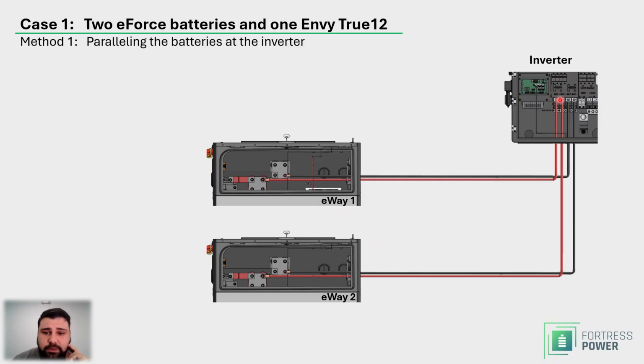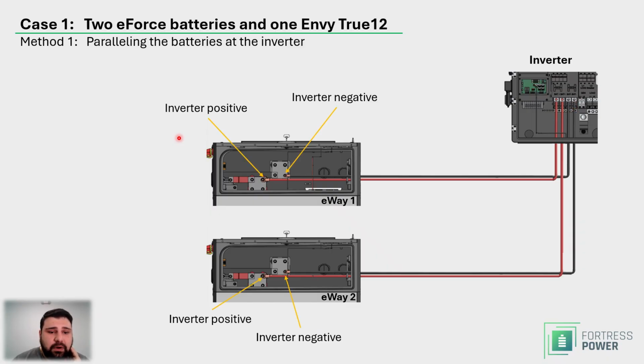Remember there are 2 positive ports and 2 negative ports in the inverter for the batteries. So 1 positive port is occupied by eWay 1, 1 negative port is occupied by eWay 1 as well, and the second positive and second negative are occupied by eWay 2, and voila. So essentially your batteries are combined and the inverter sees the combined battery bank. Very good. So inverter positive, inverter negative, inverter positive, inverter negative in both of these eWays.